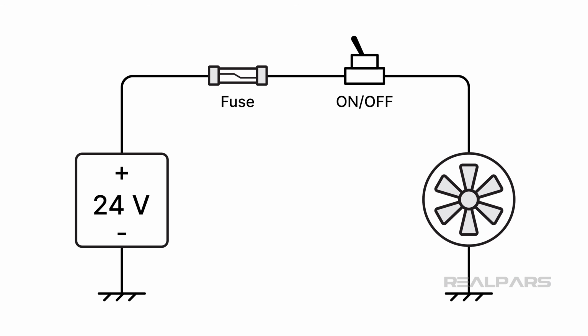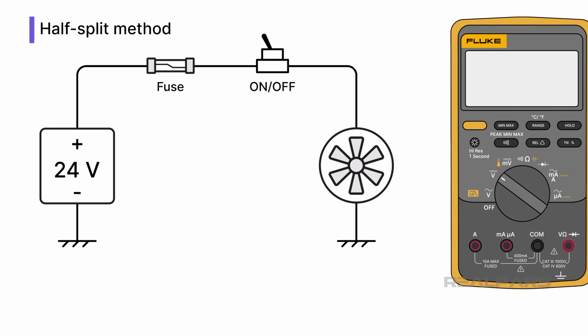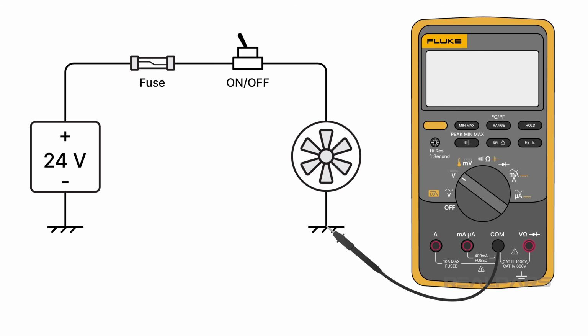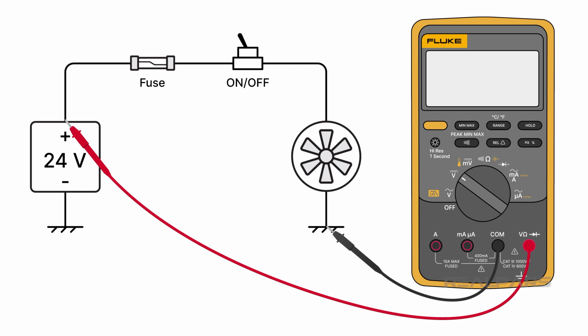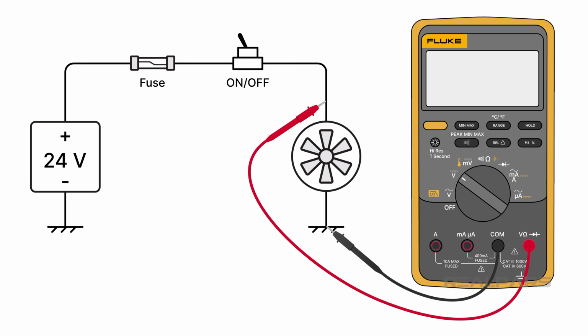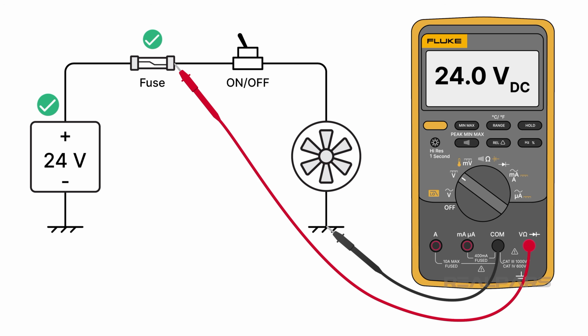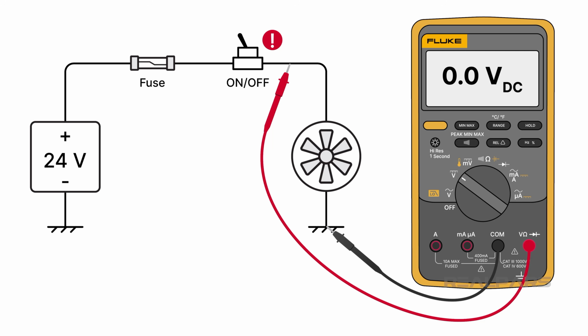Principle 5. Divide and conquer. Use the half-split method. Experienced troubleshooters don't check every component. They don't start at the beginning or the end. Why not start in the middle and eliminate half the circuit right away? If you continue with half-splitting, your troubleshooting time will be considerably reduced. The purpose of each measurement is to hopefully point you in the right direction.